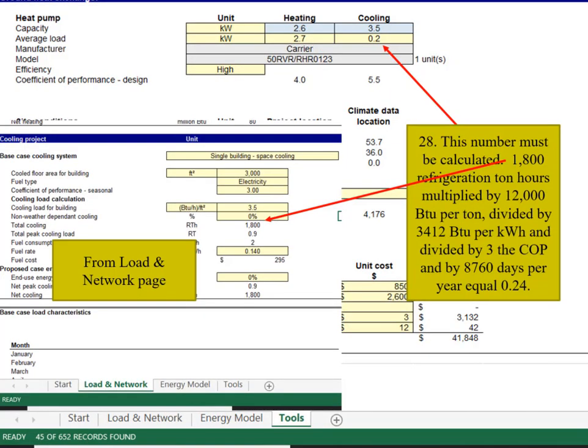Again from the Load & Network page, locate the 1800, that's the refrigeration ton hours, and multiply it by 12,000 BTUs per ton hour. Divide it by 3,412 BTUs per kWh and 3, the COP, and finally by 8,760 hours in a year to obtain 0.24.